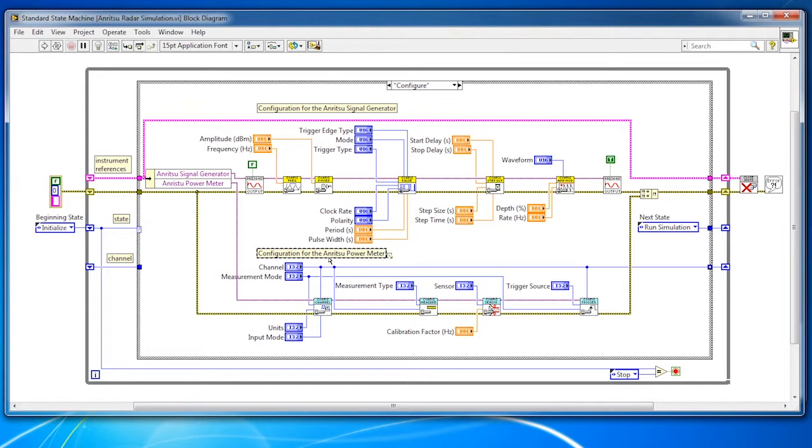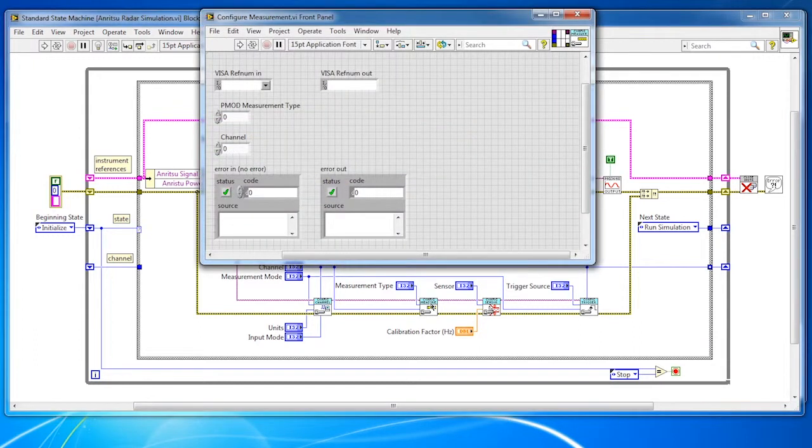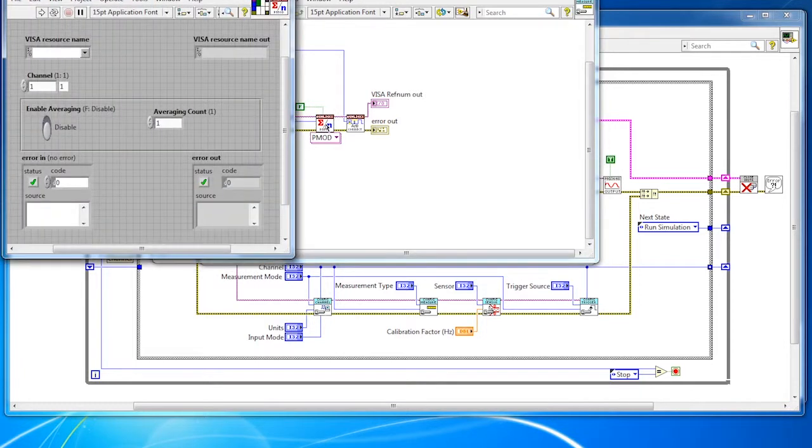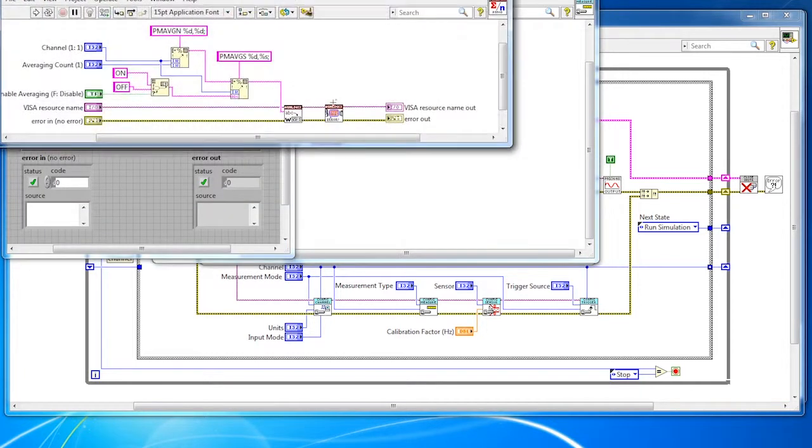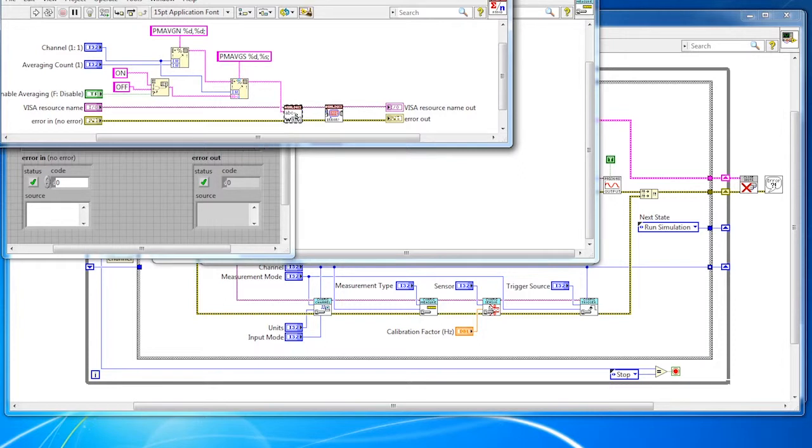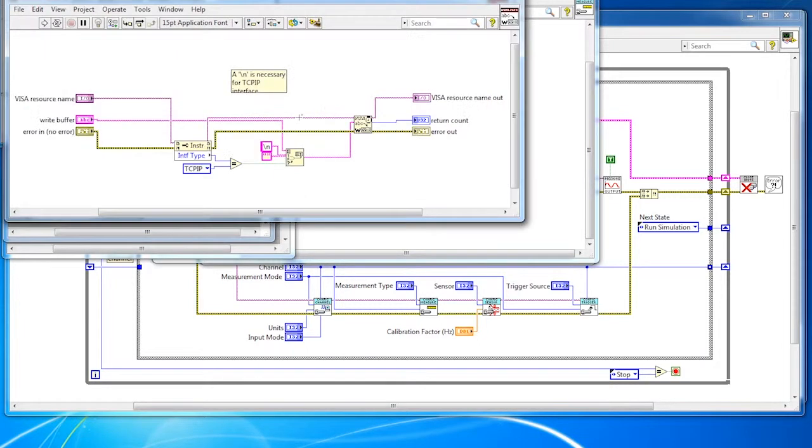If we look at the code within the configure measurement sub-VI, you will see that there are three driver calls being made. The first one is being used to configure a pulse modulated measurement. Because these instrument drivers are open source, we can open the code and examine the SCPI calls being passed to the instrument. Notice the VISA implementation under the hood of the driver function call. This is the layer that allows for interchangeability across bus connectivity.